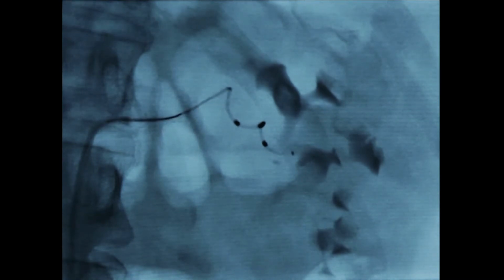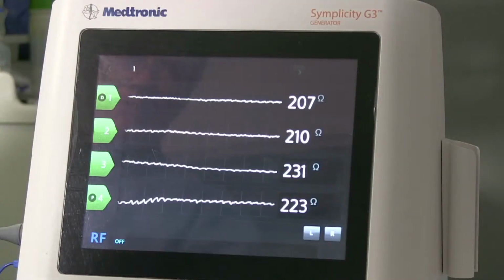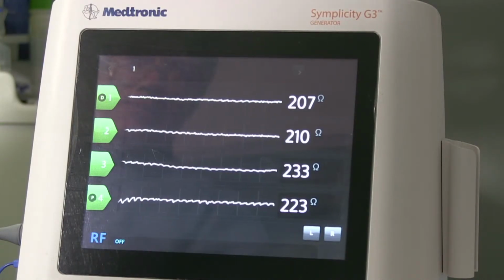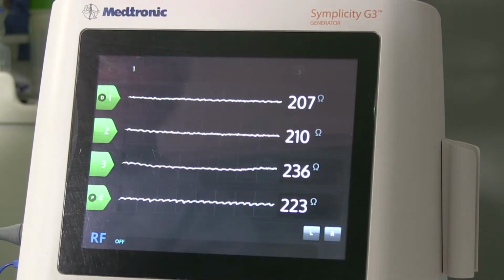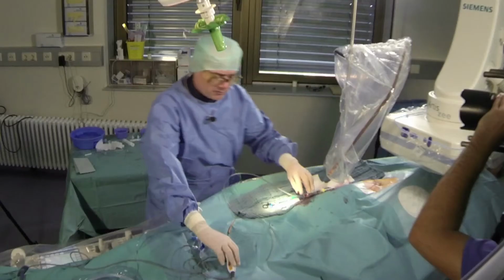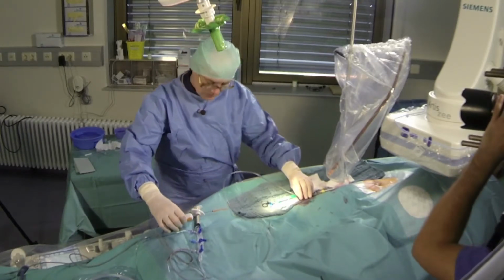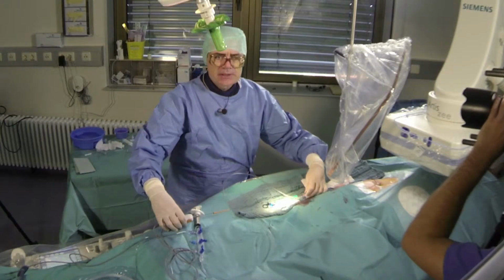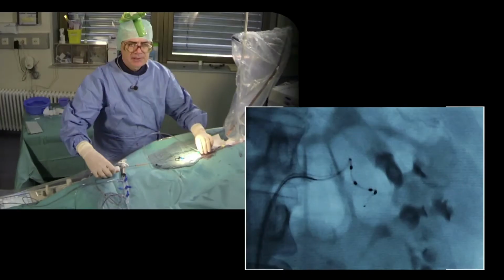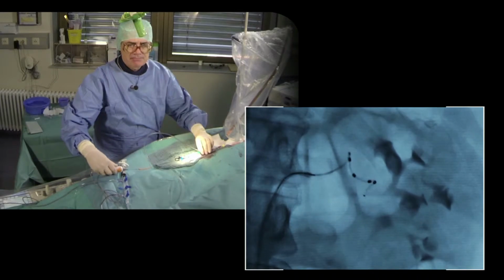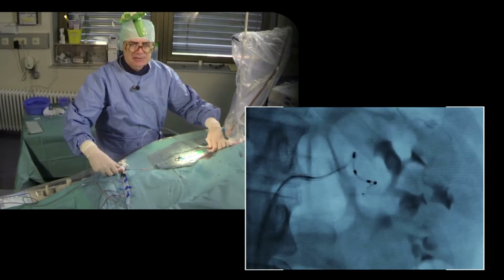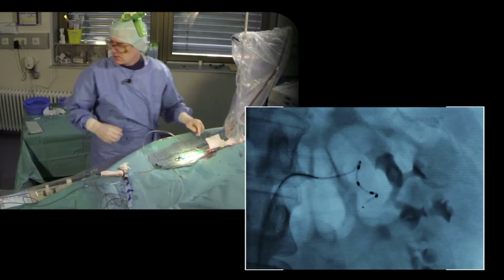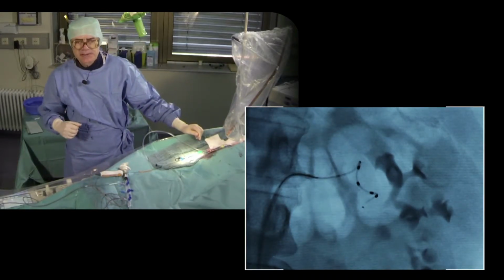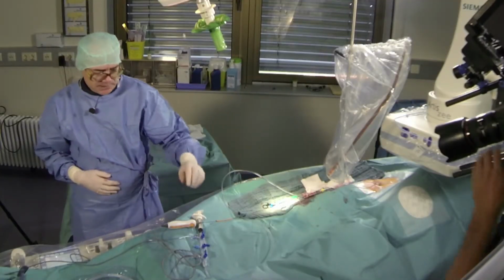Now we can see that we have 4 curves for all the 4 electrodes, and what we are looking for here before we start the energy application is basically that we have a stable impedance. The wall contact is perfect. What we can do in addition to improve the wall contact a little bit is we can turn the spiral catheter slightly, and this results then in a further increase in wall contact. So now we start the ablation cycle.